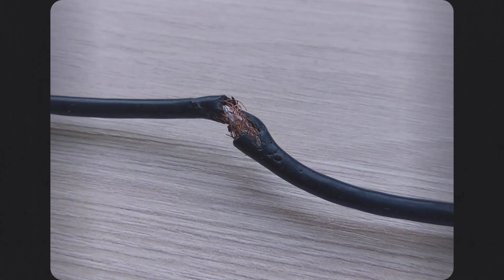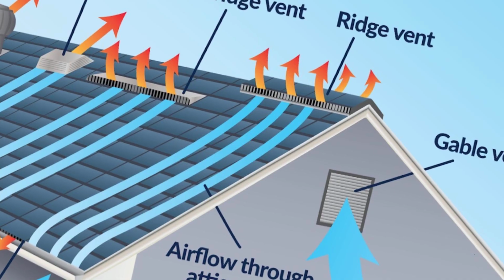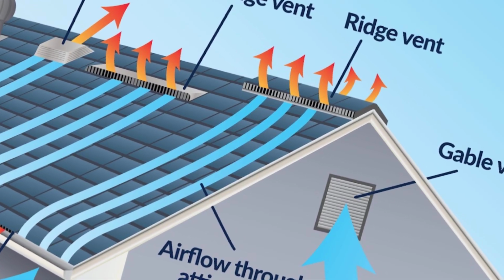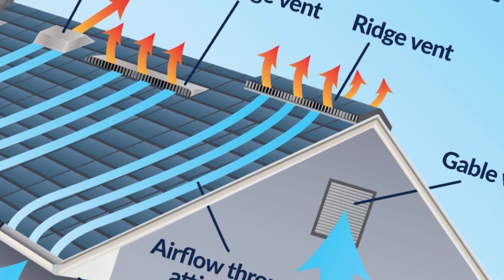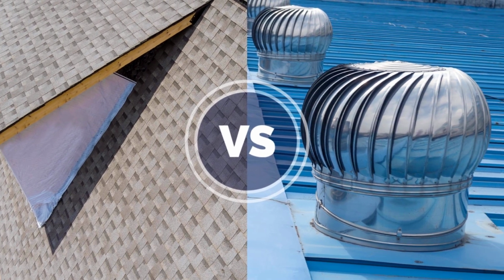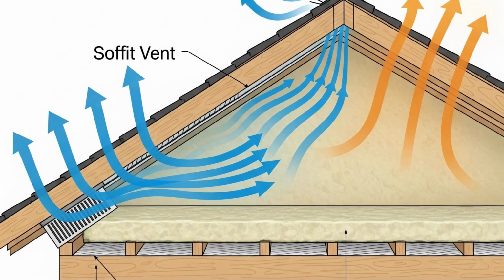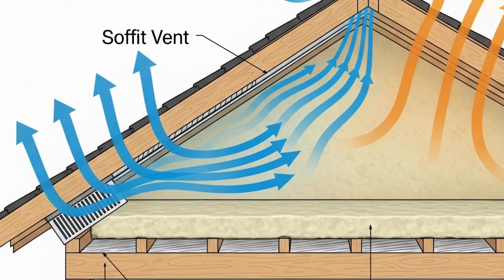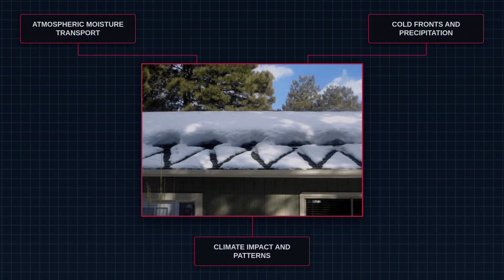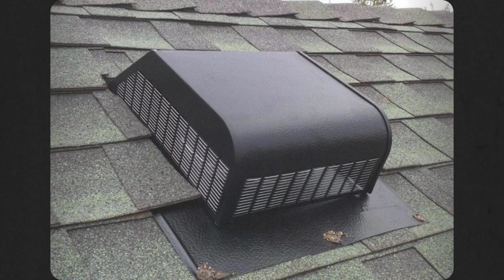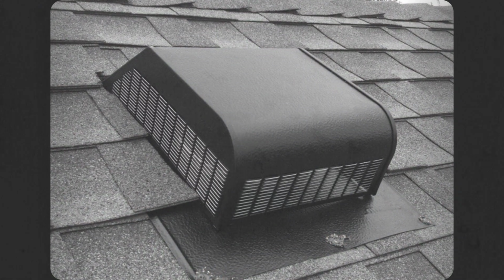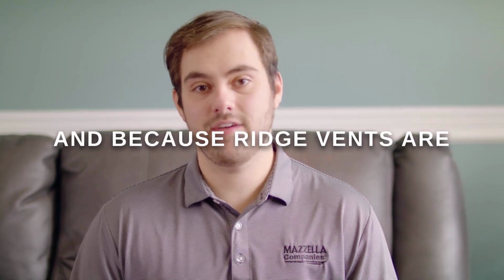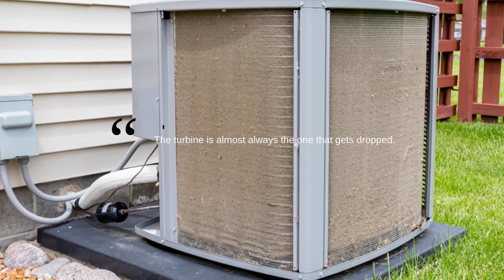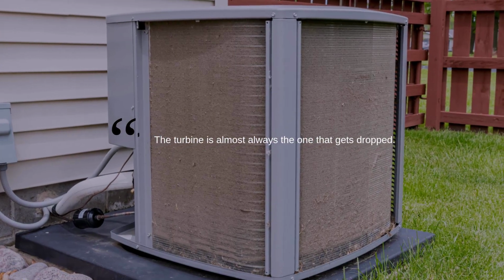The second reason is a subtle engineering problem called short-circuiting. When a turbine ventilator and a ridge vent are installed on the same roof above a common attic space, the turbine pulls air more aggressively than the ridge vent. This pressure difference can cause the ridge vent to reverse its function and start drawing outside air inward, bringing rain and snow with it instead of exhausting warm air. For this reason, roofing professionals recommend choosing one exhaust system and committing to it. And because ridge vents are simpler to install and invisible from the street, the turbine is almost always the one that gets dropped. The third reason is pure aesthetics and neighborhood politics.